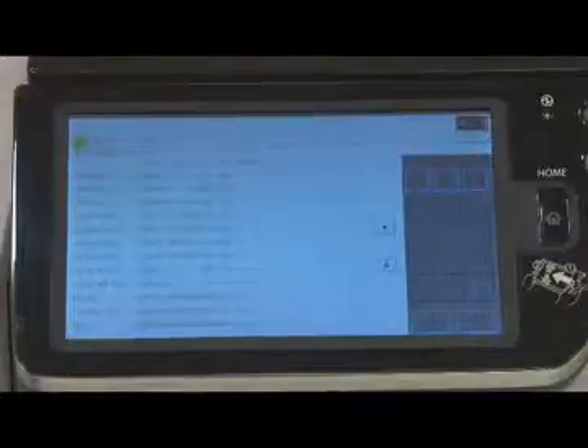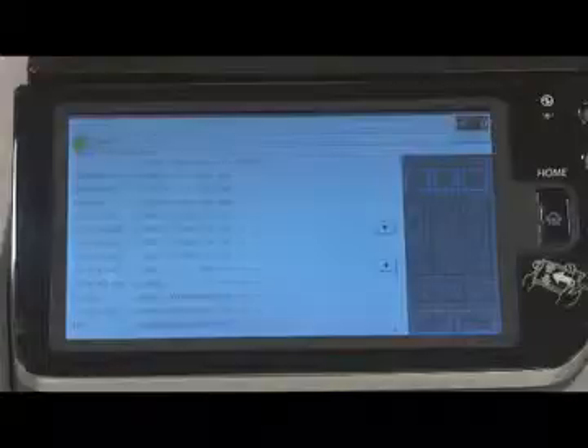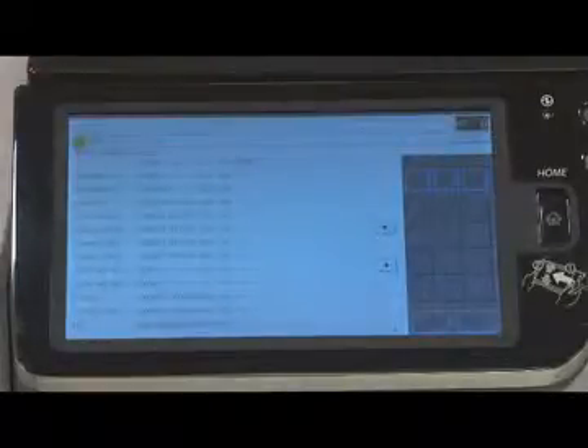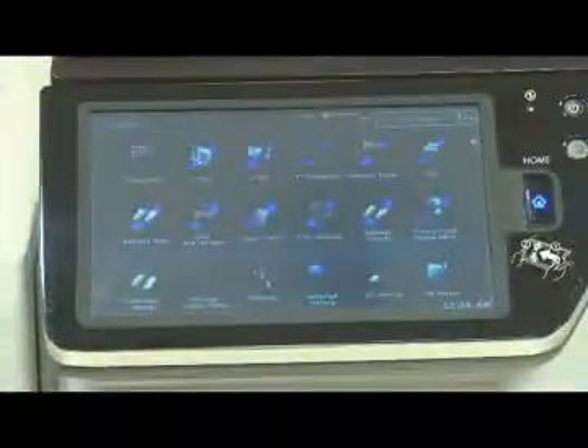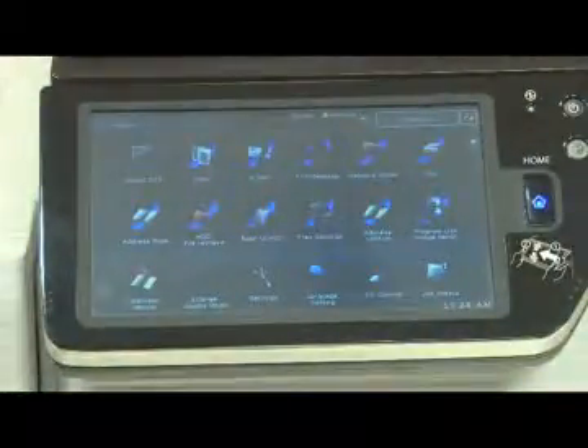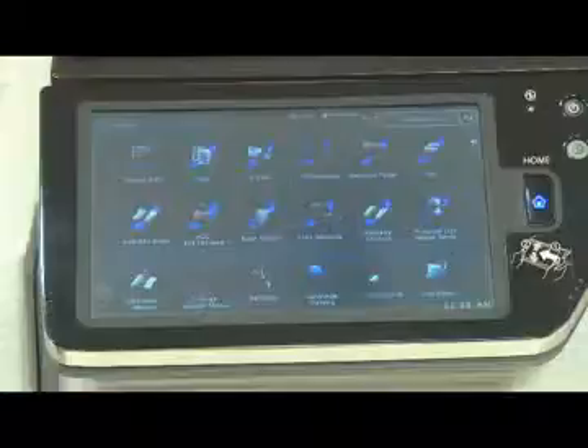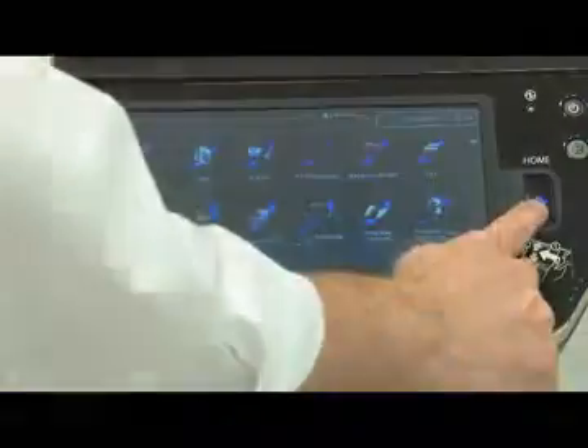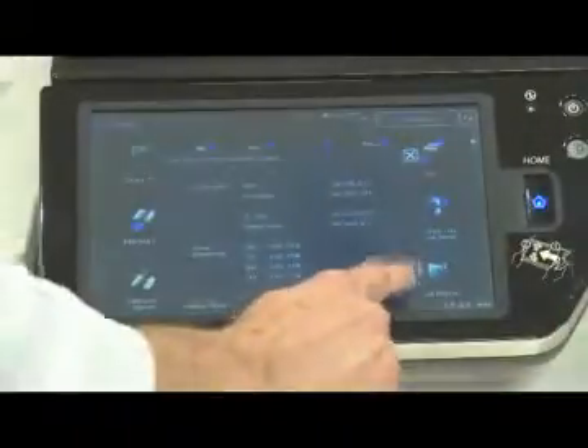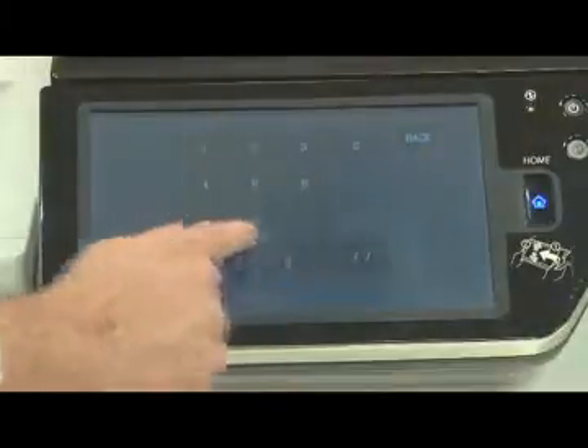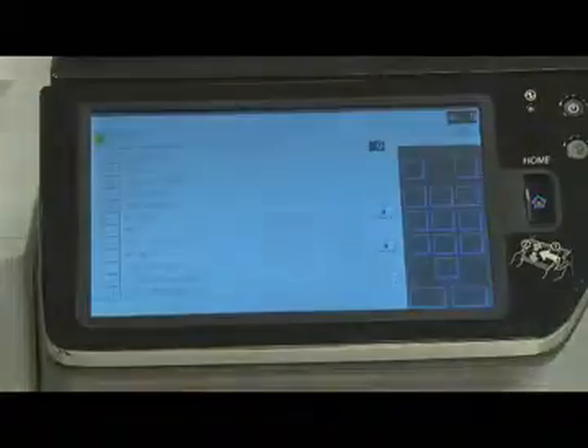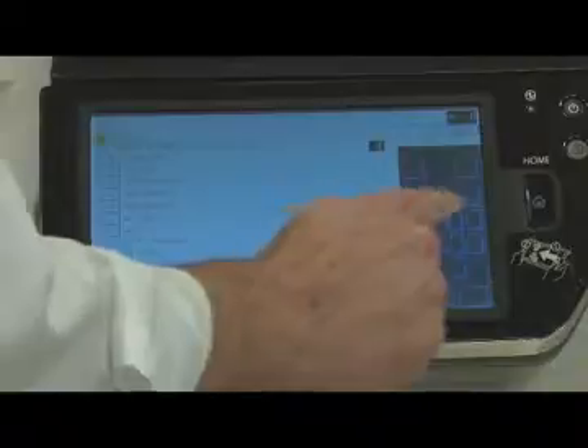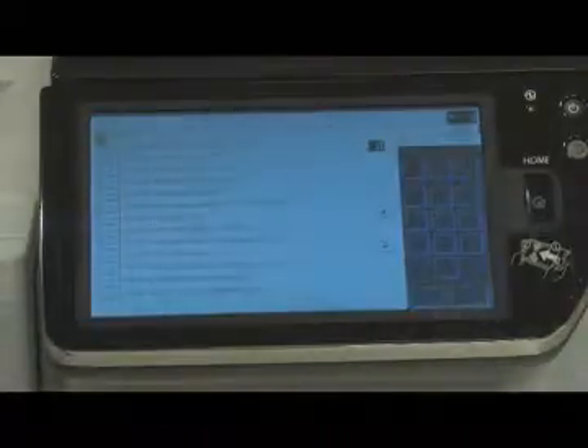So at this point, the next thing we need to do is color calibrate the machine. So that would be the next procedure. So the next thing that has to be done is we have to calibrate the machine. We have to do the color balance adjustment. So we're going to enter simulation mode. And we're going to enter simulation 46, subcode 74.